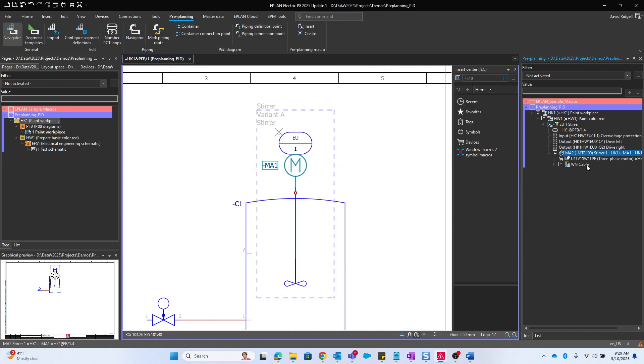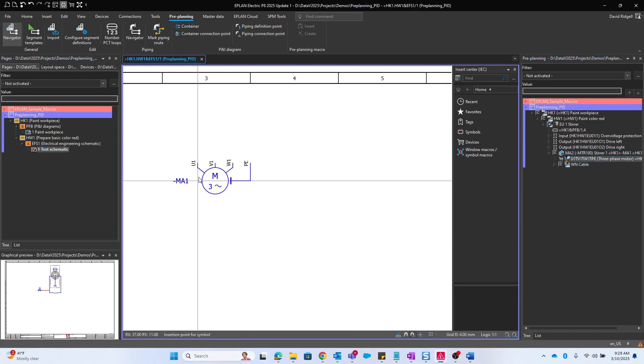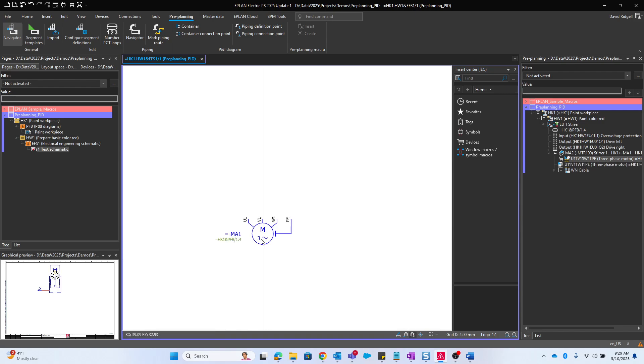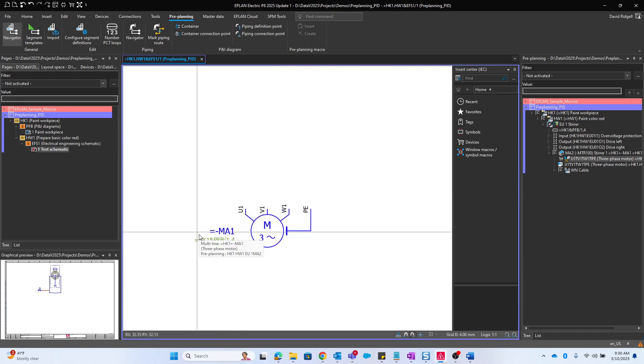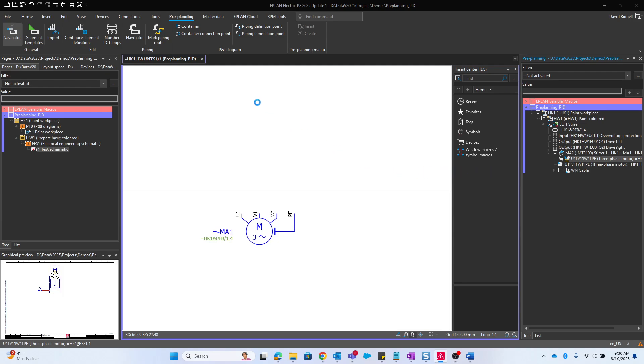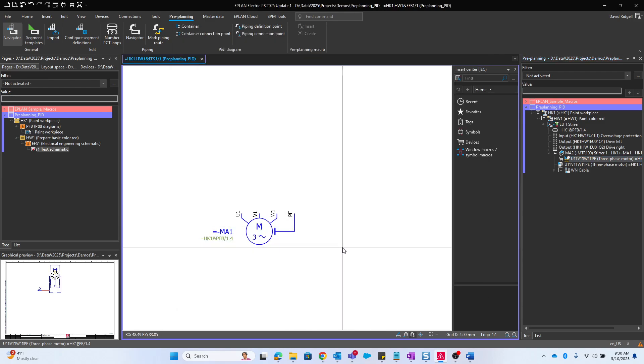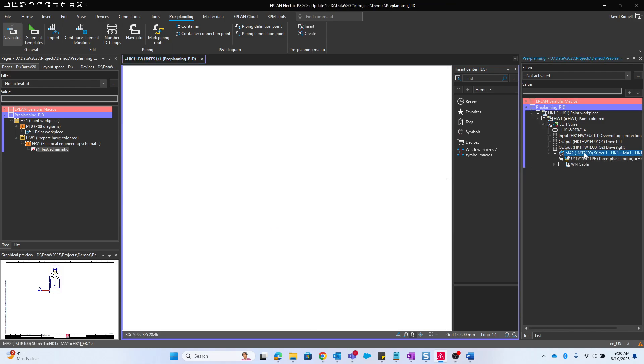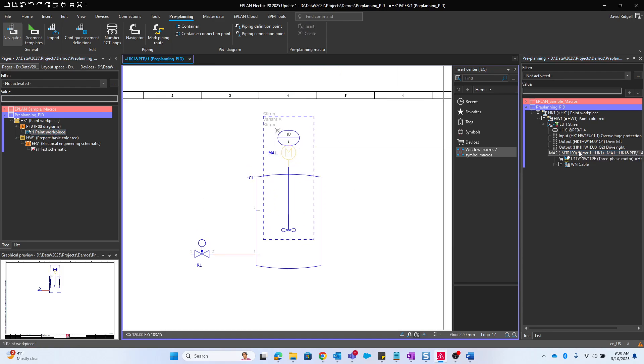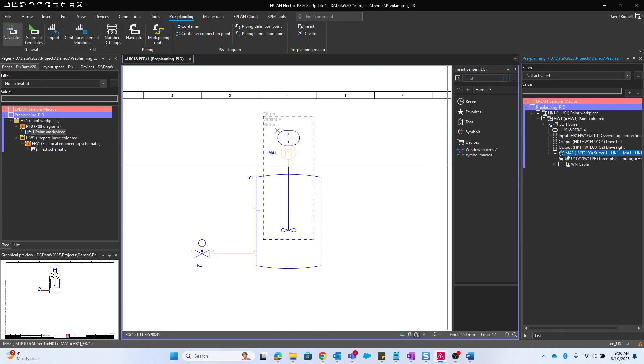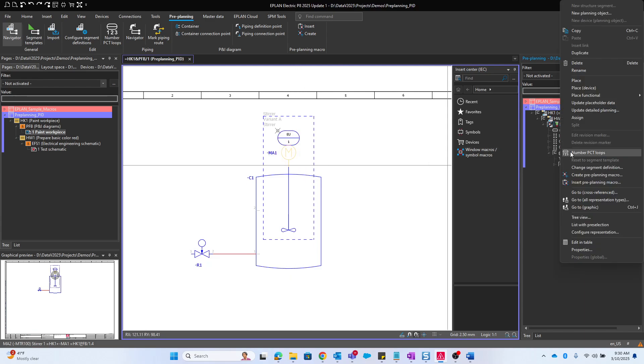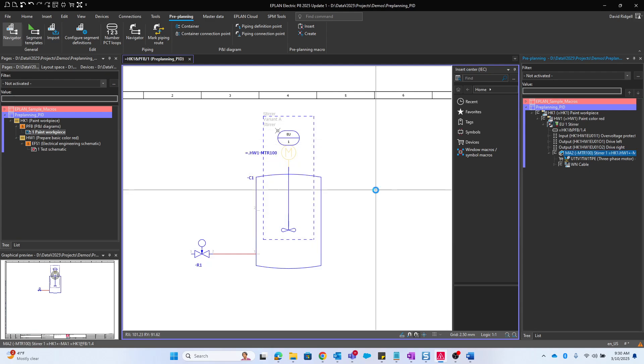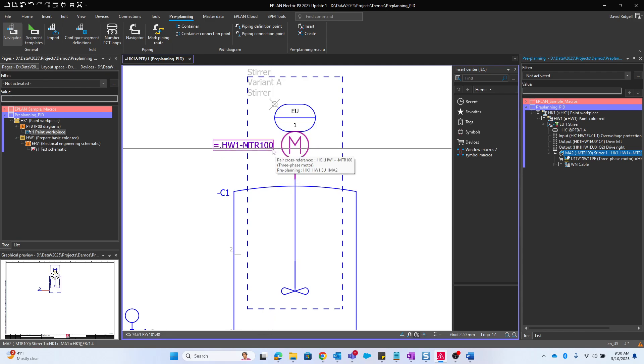We can also control this from the product aspect. If we go to the properties of the planning object, this is basically where you can preset the device tag of the electrical detailed component. So if I said this was MTR100 for example, we see that it's MA1. The reason why it didn't pick up that MTR100 is because the main function was already set here at the counterpart of the PNID as MA1. If I go back to my PNID, remember I set the product aspect here at the planning object. How do I update that here and then place it in the schematic? I can right-click and say update detailed planning, making sure that we're updating device tags for sure. Now we'll see that it does pick up that new device tag.